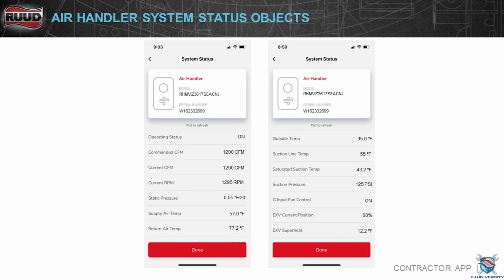Suction pressure, once again, it's reading off of that suction pressure transducer that also controls the low pressure cutout in heating and cooling. If you have an EEV, it'll give you your EEV superheat and current position of the EEV. So it's going to tell you what position, whether it's completely open, completely closed, or somewhere in the middle, which is good to know a lot of times, on where your EEV is actually sitting. So if you're seeing something funny on your superheat, and it's showing that it's open, but it may not be, or it's stuck or something like that, this is reading the actual stepper motor position.